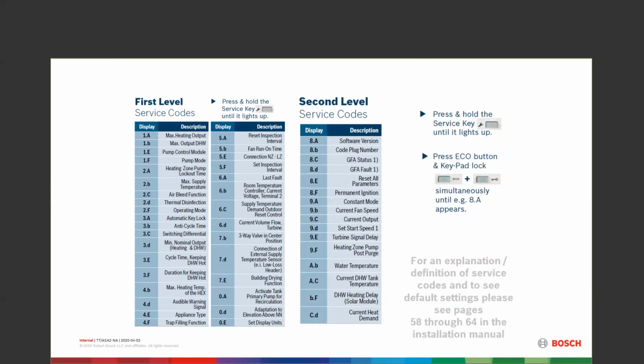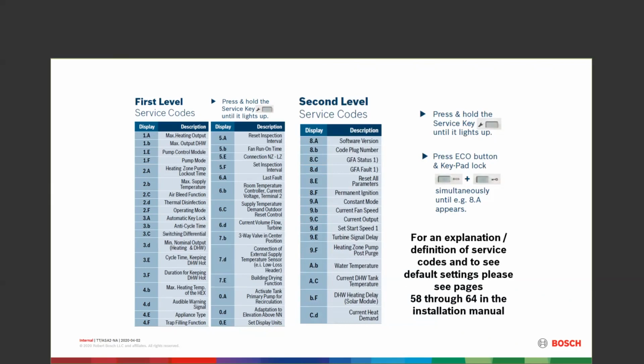So go into the manual, look through these things, and use these service functions to help you in troubleshooting. For instance, on a domestic hot water call where the boiler goes to limit right away and we still get no domestic, first I go to 6D. I see what my current flow rate is. If I have 1.5, 2 gallons a minute, next I go to make sure I have the right current demand. Do I have domestic hot water? So C.D should show me 0.2. And then I go to A.B and see what the water temperature is coming out.